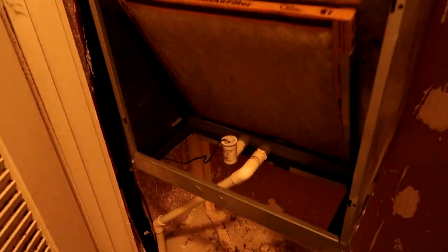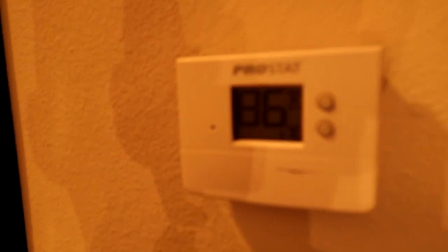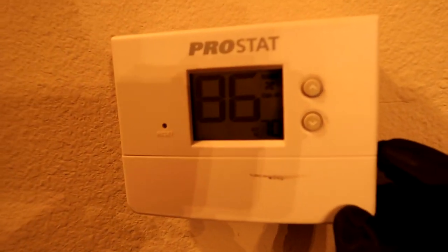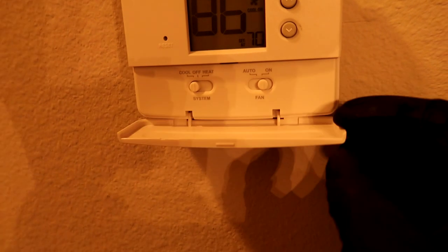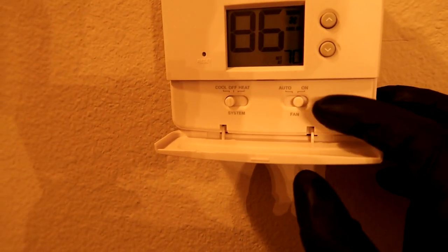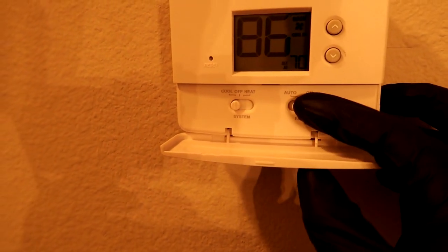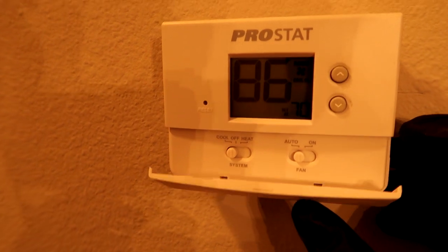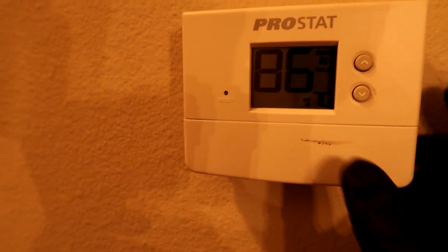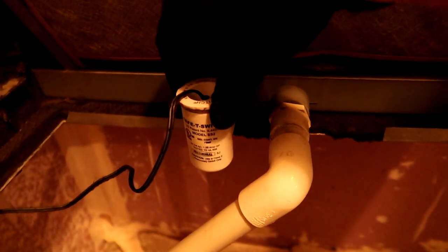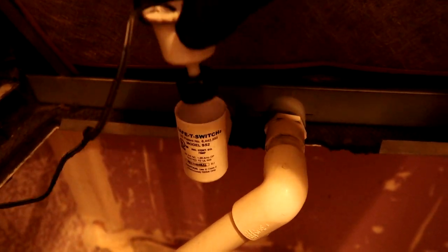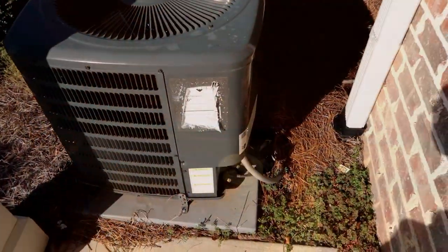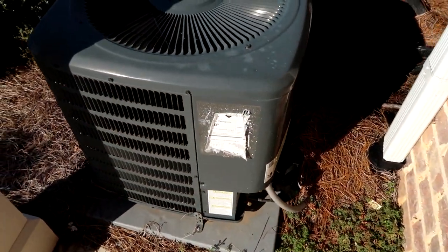All right, we got a no cooling call. Filter looks good. 86 degrees in here, set to 70. Third floor, it is hot. Hopefully it's just the float switch. No, bone dry. Let's go outside and see what's going on with the condenser.